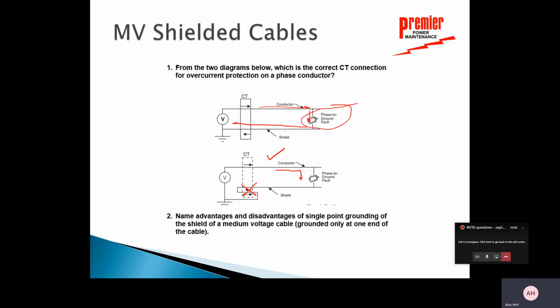Now, name the advantages and disadvantages of single point grounding of the shield of a medium voltage cable, grounded only at one end. So what would be the advantages of that? Well, number one, since it's only grounded at one end, there are no induced currents. There's not a path for current to flow in that shield. But a separate ground wire has to be provided, so I have a path for fault current and ground current to return, but it wouldn't be going through the shield. So I'm actually saving that shield from that current.